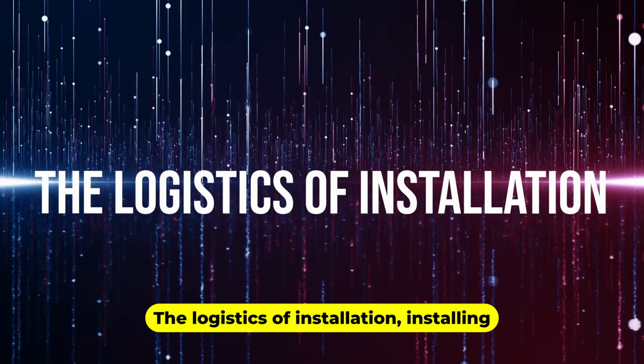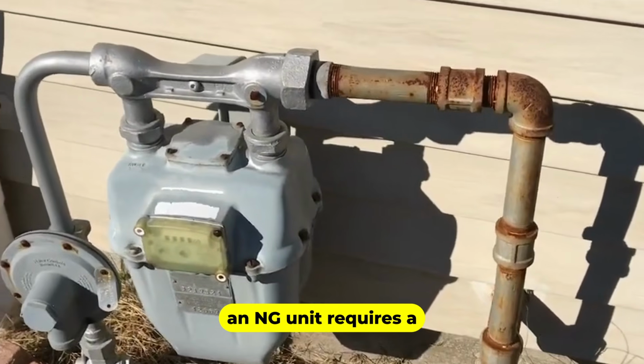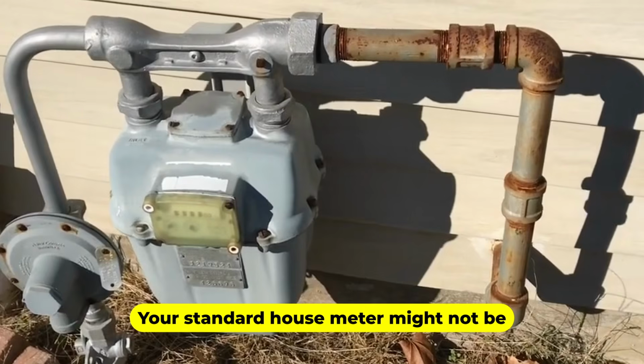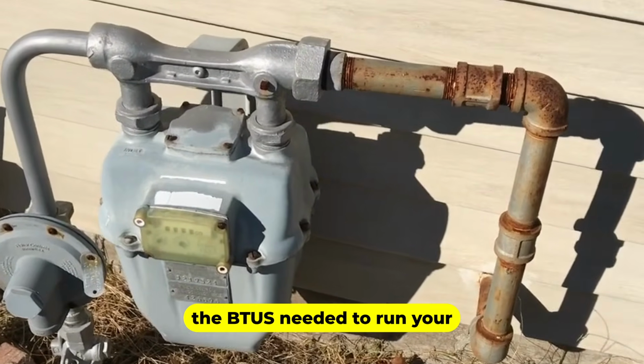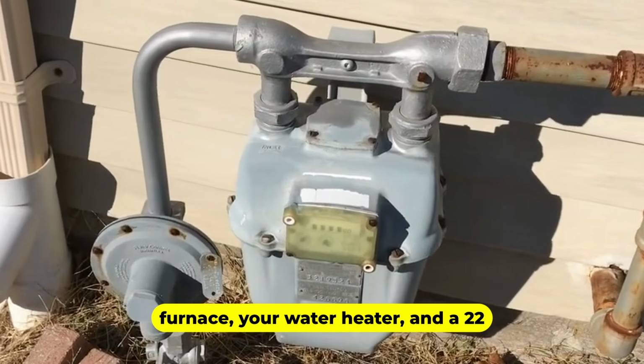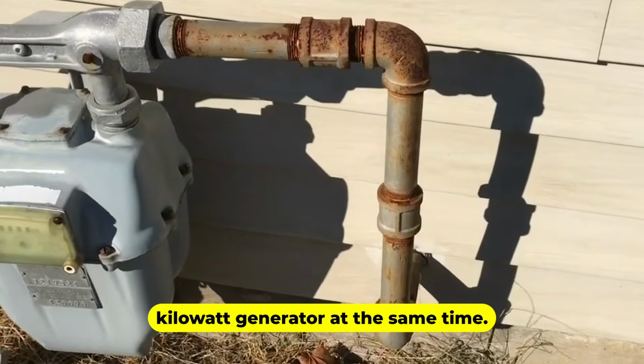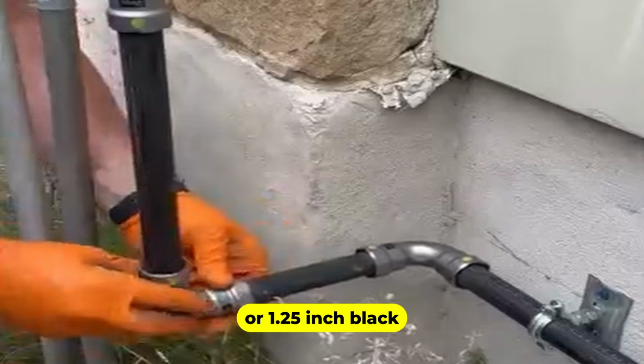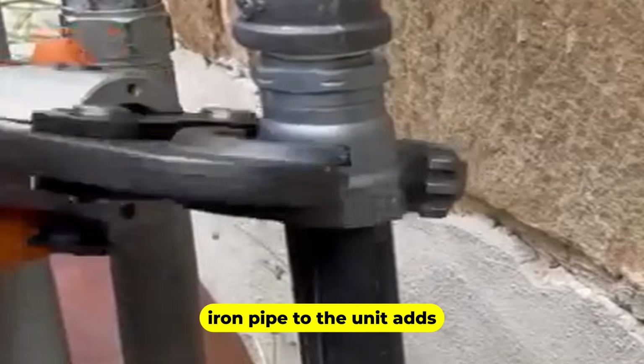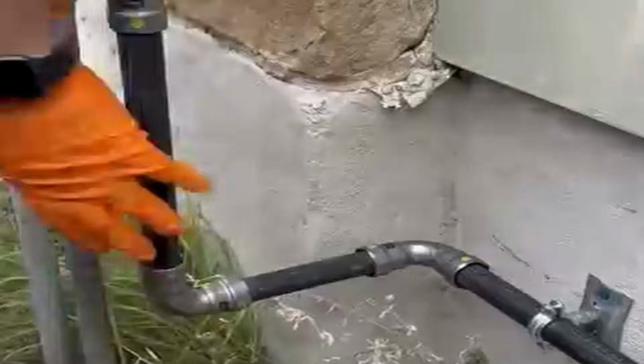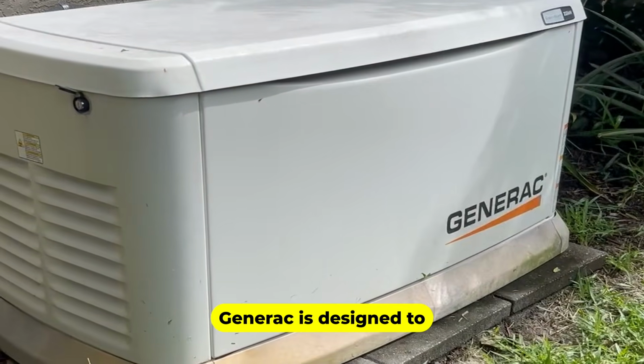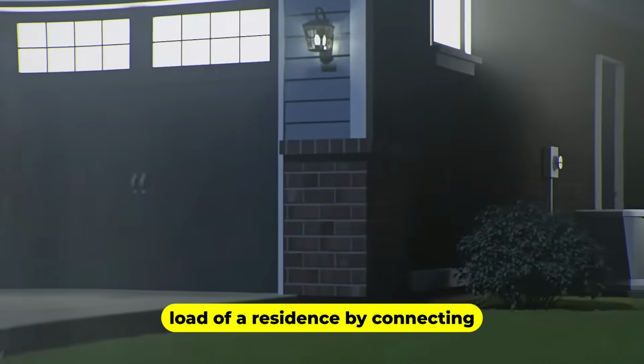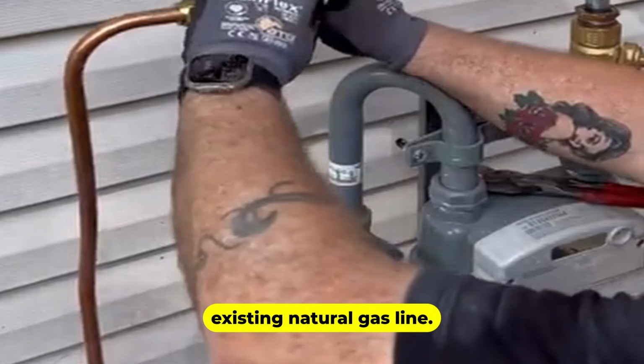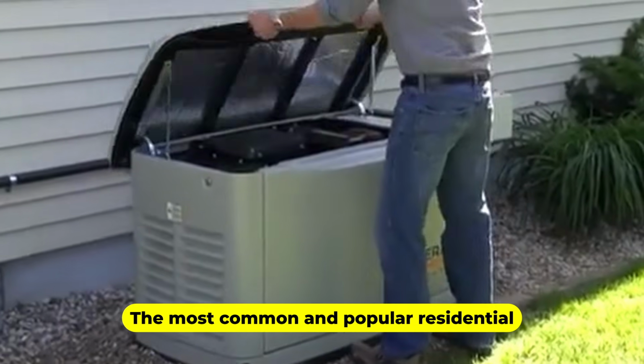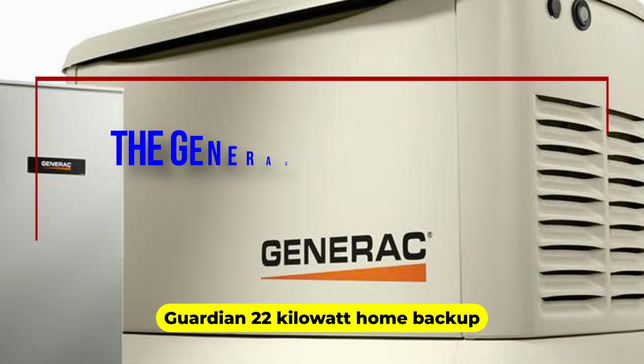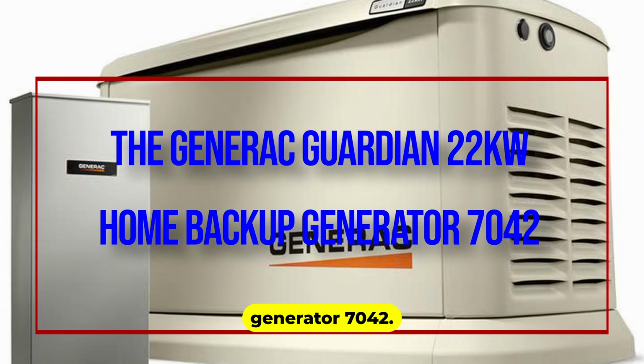The logistics of installation. Installing an NG unit requires a high-volume gas meter. Your standard house meter might not be large enough to provide the BTUs needed to run your furnace, your water heater, and a 22 kilowatt generator at the same time. Upgrading that meter and running 1-inch or 1.25-inch black iron pipe to the unit adds significantly to the complexity of the job. A whole home natural gas generator from Generac is designed to handle the entire electrical load of a residence by connecting directly to your home's existing natural gas line. The most common and popular residential model is the Generac Guardian 22 kilowatt home backup generator 7042.